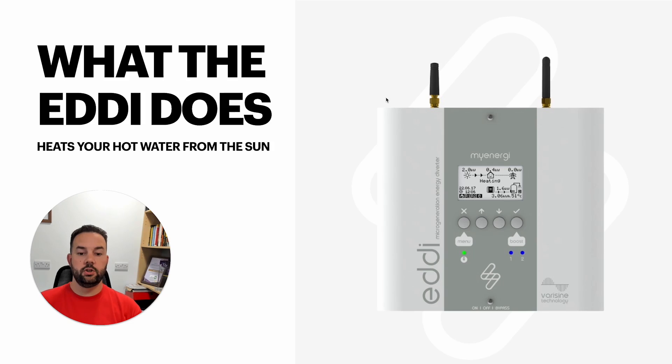In addition, if you're in the myenergi ecosystem with other devices, you can set priorities. So Zappi might go first and charge your car, and then the eddi takes up the rest. That's also useful when your Zappi is waiting for surplus — it won't react until it sees 1.4 kilowatts. If that's not available, you can have that power go into the eddi instead. That's the simplest way of how the eddi works: it's basically an on and off switch for your immersion heater that comes on to match the available solar power.